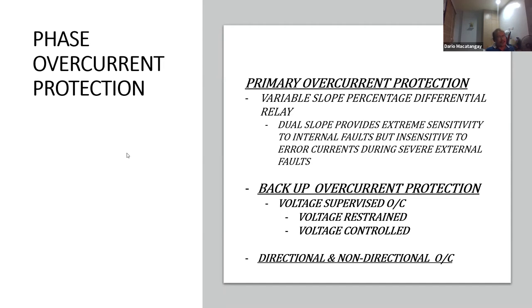This is intended to back up the differential protection. Under load condition, voltage is normal, and the voltage will restrain the overcurrent element. When there is a fault, the voltage becomes low, the voltage restraint picks up, and allows the overcurrent to trip the circuit. So that's your backup overcurrent protection.